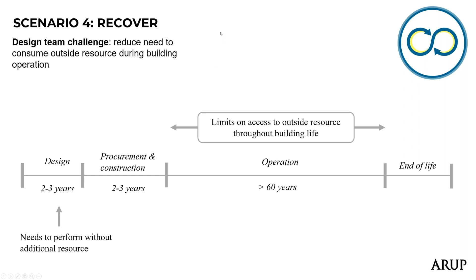For the Marshgate building, we took passive as our starting point, and any equipment we retained, we upgraded to high spec to make the most of high efficiencies and reclaim as much energy on site as possible, so we weren't consuming external resources. We also swapped the connection to district heating for ground source and air source heat pumps, again to recover as much wasted heat on site as we could. We gave a lot of consideration to improving the building envelope's performance to save as much operational energy as possible, which highlights how this impacts not only MEP and building services but is really a cross-discipline design approach.